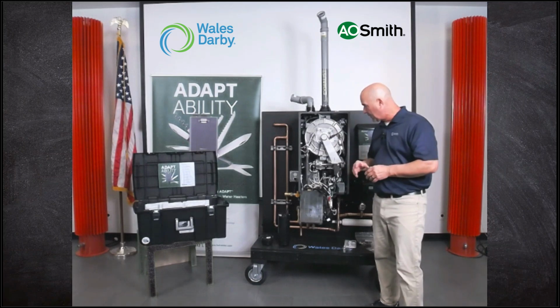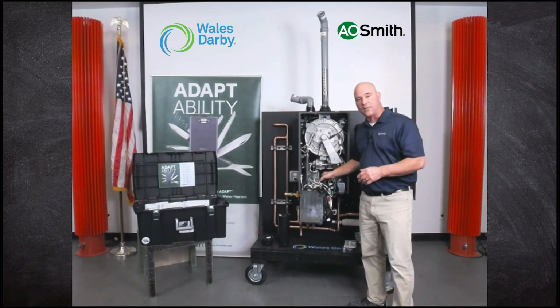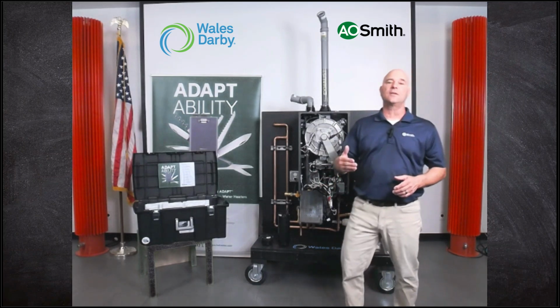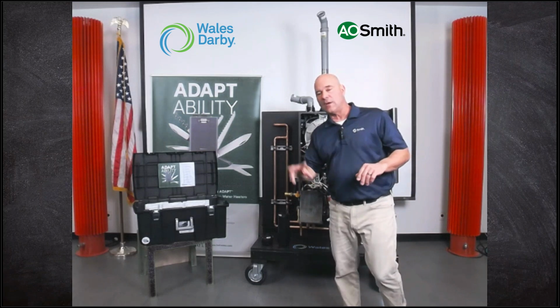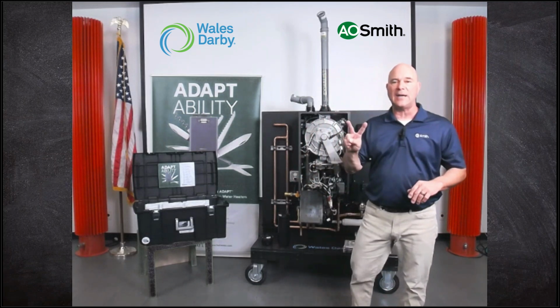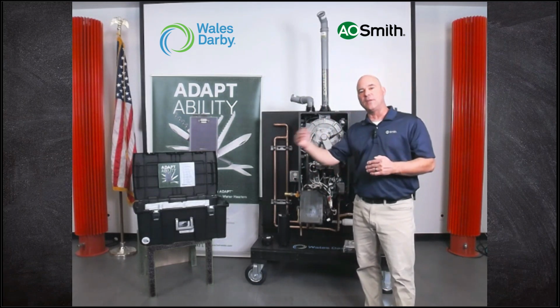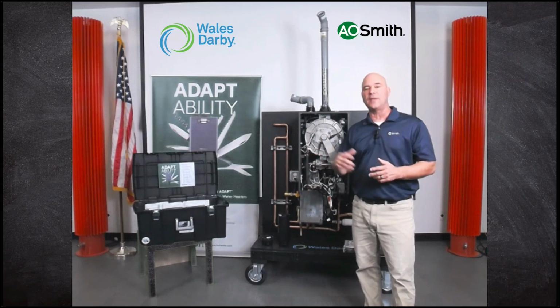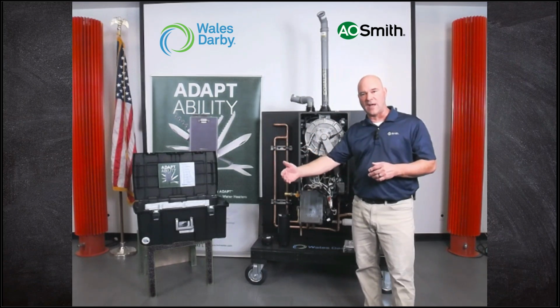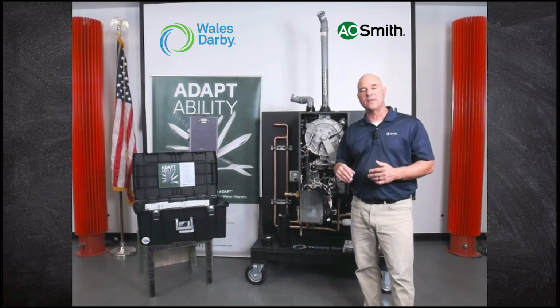We got a lot of room to work within the unit. We have a built-in circulator. Out of the box, the circulator comes in the off position. You have the opportunity to give it 2 different times to run. It can be with either a dedicated return line or with an A.O. Smith crossover valve. That will meet our minimum flow rates.